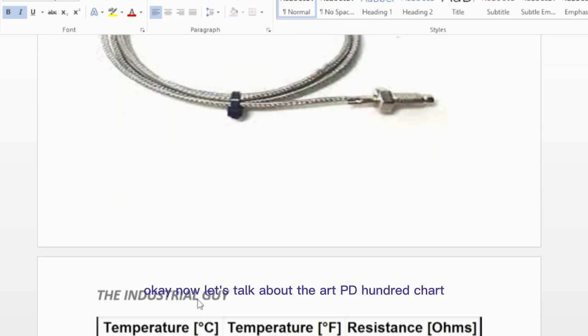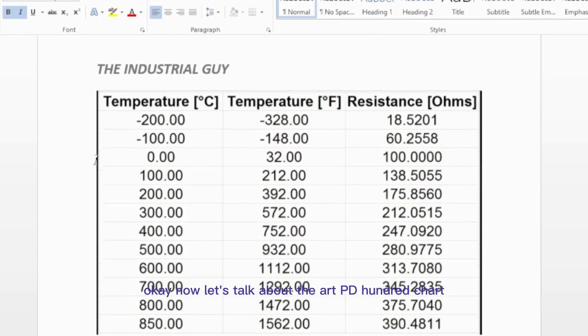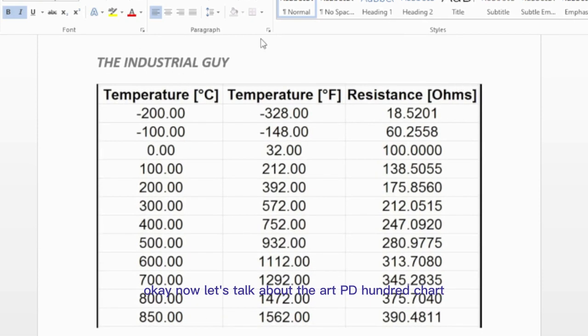Now let's talk about the chart. This is the PT100 chart. We use this chart to troubleshoot problems related to PT, and also for designing. You can see the first column is temperature in degree centigrade, the second column is temperature in Fahrenheit, and the third column is resistance in ohms.